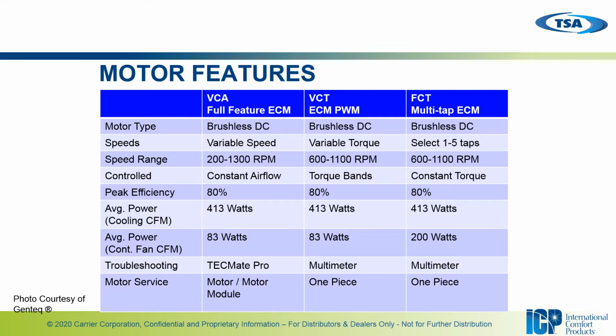And the fixed constant torque motor is often referred to as a multi-tap ECM, standard ECM, or an X13 motor. As a brushless DC motor, it has a speed tap selection and a speed range of 600 to 1100 RPM. It is a constant torque motor with 80% peak efficiency, just like the other two. The average power consumption in cooling is 413 watts, the same across the board. However, on the constant fan you are limited to speed, so it has a little bit higher rating at 200 watts. This also can be troubleshot with a multimeter and is a one-piece motor as well.